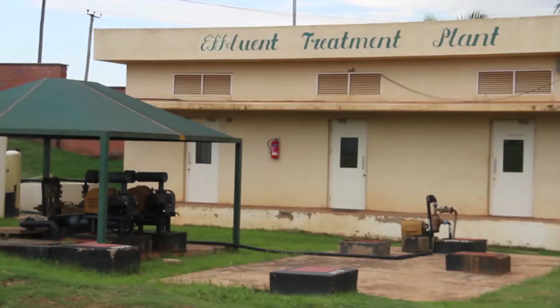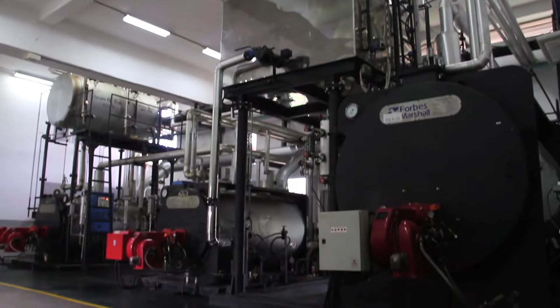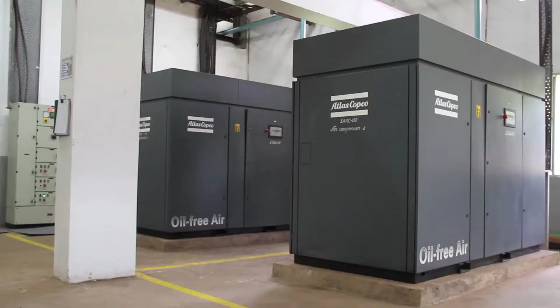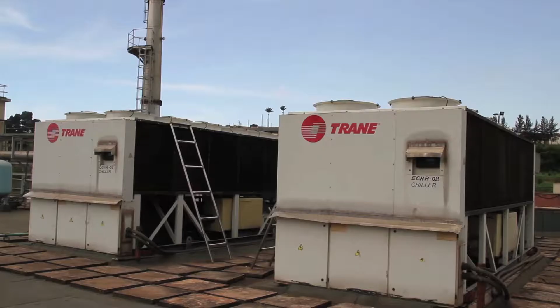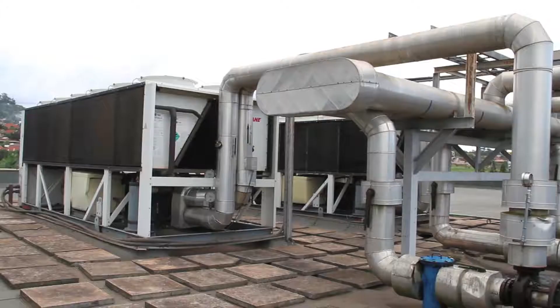The plant consists of the main building, a utility house adjacent to the main building, and an effluent treatment center. The utility plant has 3 boilers to supply filtered steam to production, 2 air compressors, 2 chillers to cool the air to required temperatures, and 2 transformers and diesel generators.